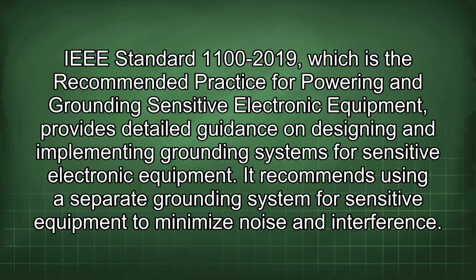IEEE Standard 1100-2019, which is the recommended practice for powering and grounding sensitive electronic equipment, provides detailed guidance on designing and implementing grounding systems for sensitive electronic equipment. It recommends using a separate grounding system for sensitive equipment to minimize noise and interference.